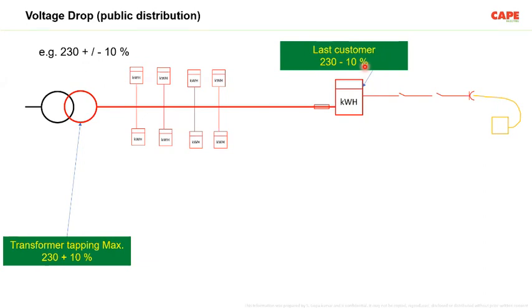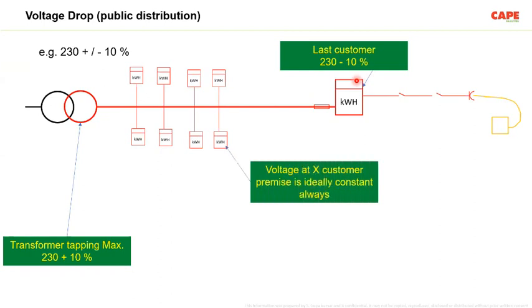Lesser voltage is a problem to the consumer premise. So the minimum voltage at the consumer premise is 230 minus 10%. So the transformer is 230 plus 10%, the consumer premise 230 minus 10%. It means a customer who is at X distance, his voltage is actually stable. It may be 230, for example, the first consumer, always his voltage is 230 plus 9%. And probably another customer is always 230 minus 9%.